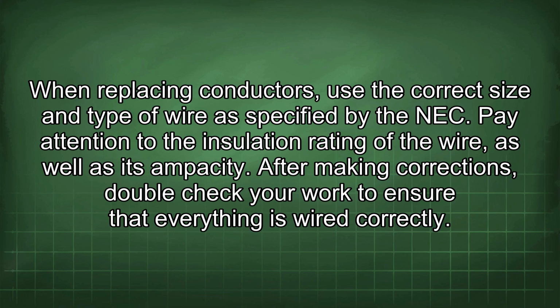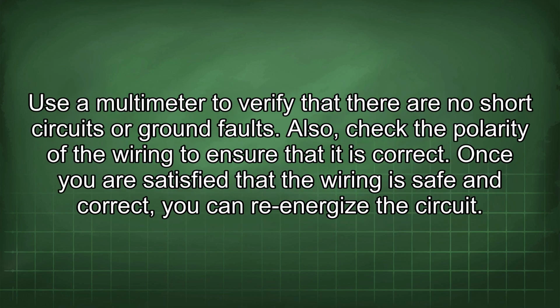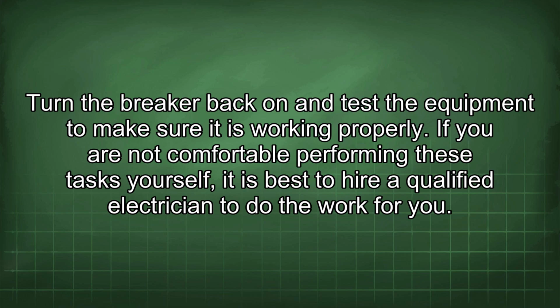After making corrections, double-check your work to ensure that everything is wired correctly. Use a multimeter to verify that there are no short circuits or ground faults. Also, check the polarity of the wiring to ensure that it is correct. Once you are satisfied that the wiring is safe and correct, you can re-energize the circuit. Turn the breaker back on and test the equipment to make sure it is working properly.